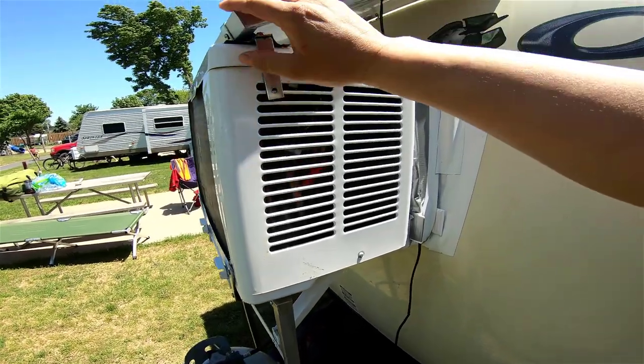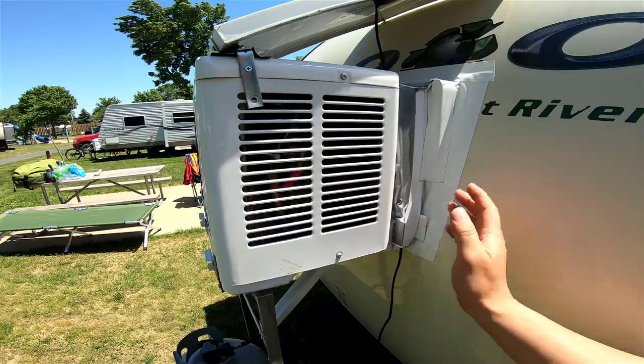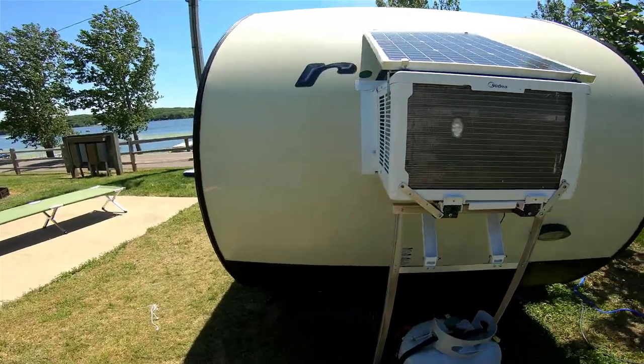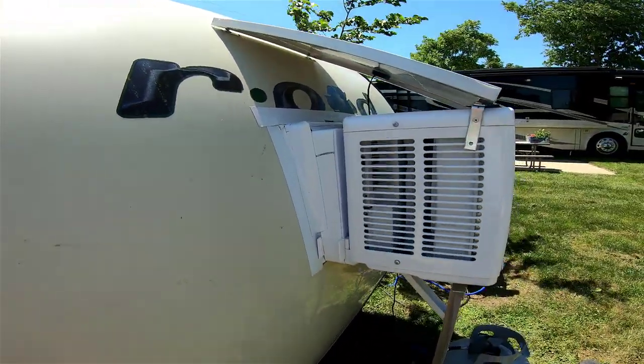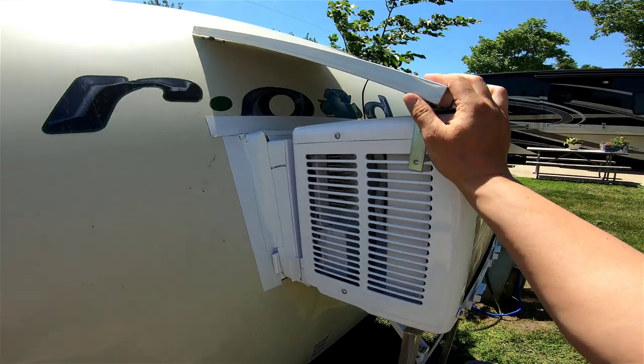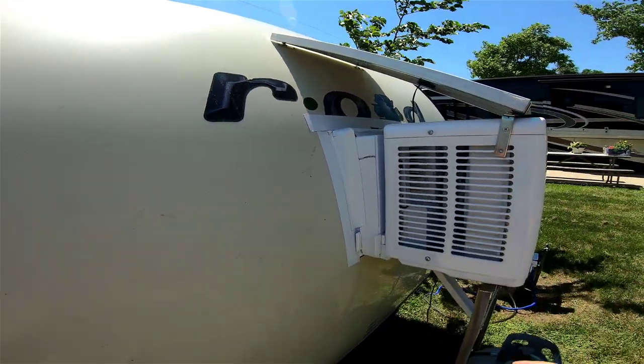The solar panel has an aluminum frame, so it gives a better holding position. It's worked really good. I haven't really tested the solar panel fully yet, but so far I think the 50 watt solar panel is not really strong enough to charge the batteries. I'll do more testing and get back to you with a report on that.